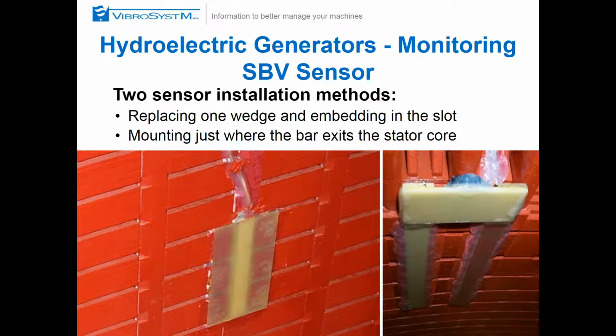Okay, so we have a picture of 2 different models here. The one on the left is a standard, looking at the bar through the slot, where the wedge is removed. And the other one is for those who do not want to remove wedges or ripple springs. You can monitor the vibration of the bar just as it exits the core.